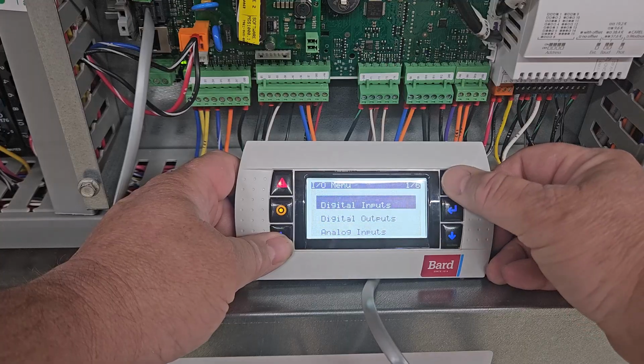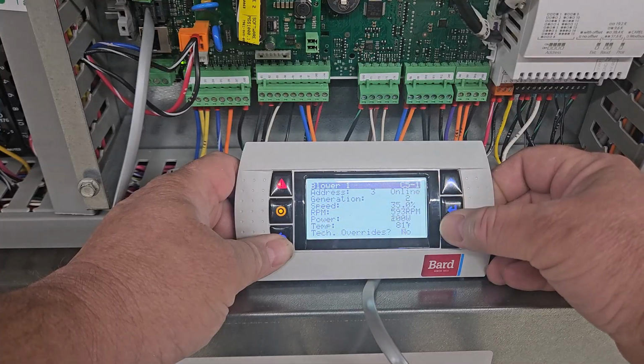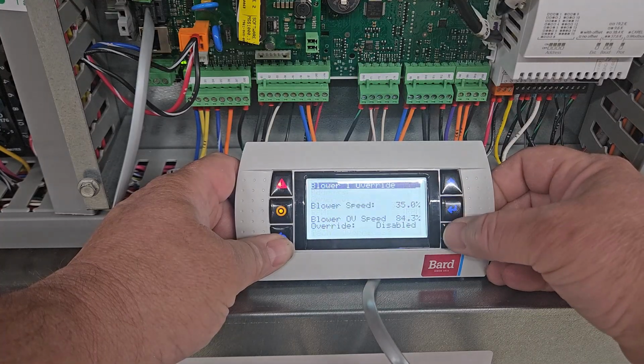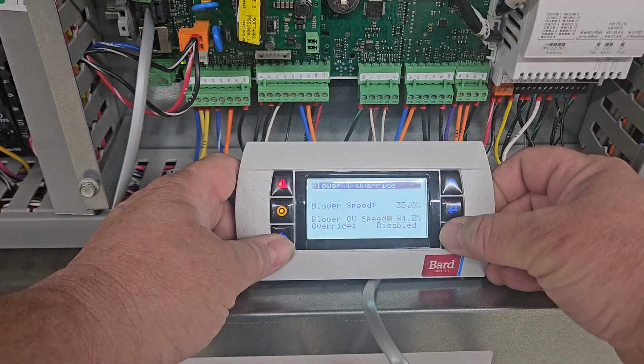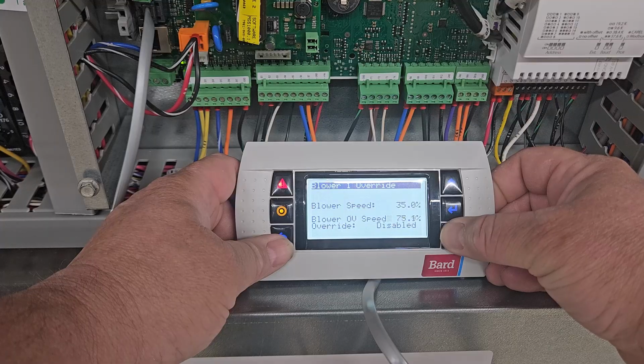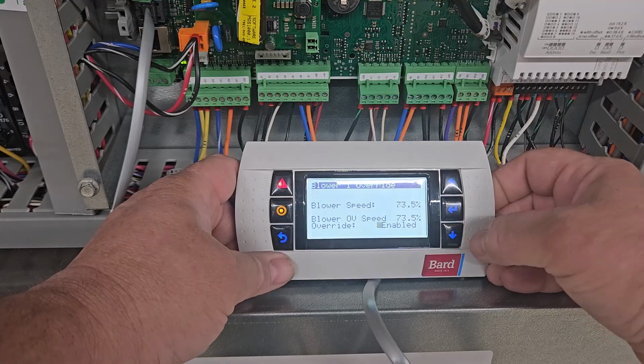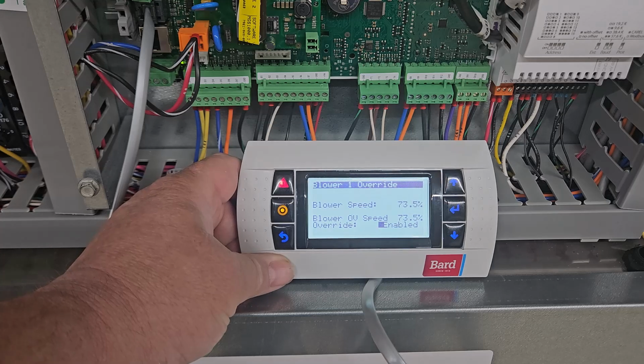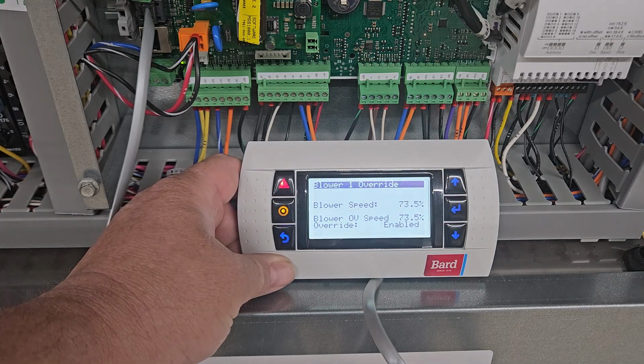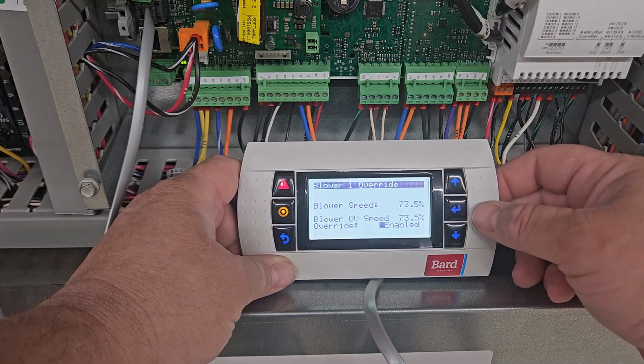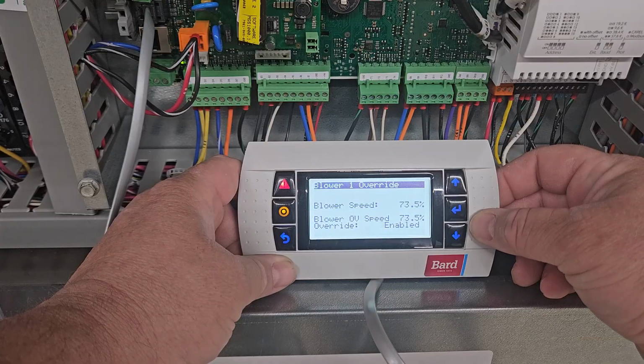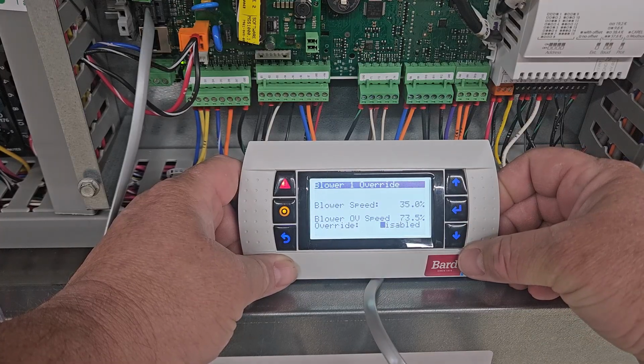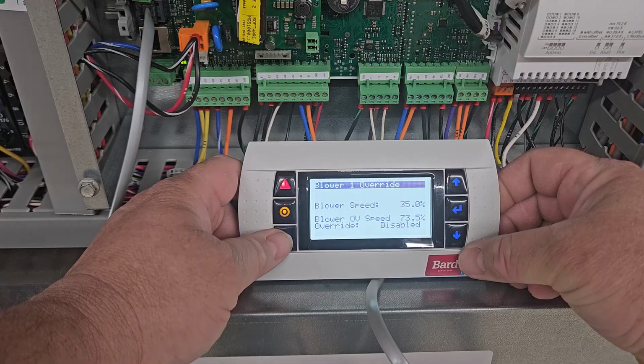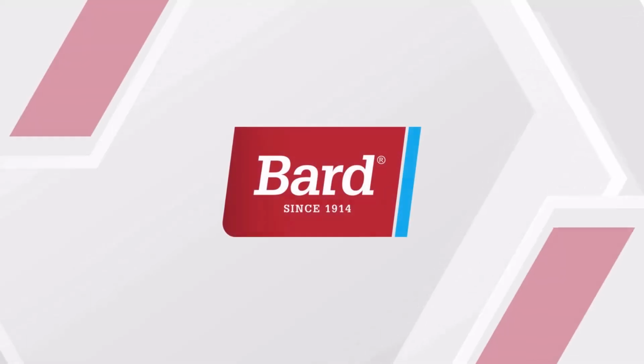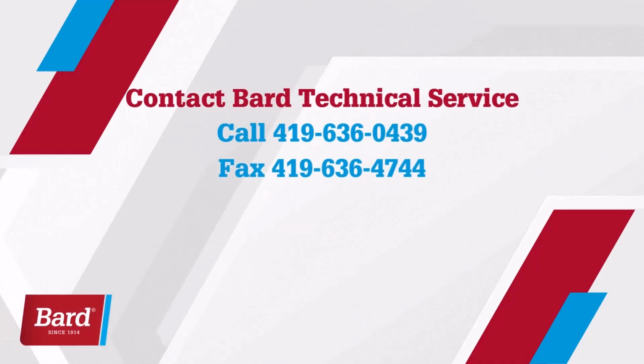Navigate to the Modbus devices and find the evaporator or blower fan. Press the override button and say yes, and then adjust the fan speed up and enable operation. The fan will start to operate at this moment. We can listen to the motor ramp up in the speed and verify the blower motor operation. At this point, let's clear any overrides and place the unit back into operation.